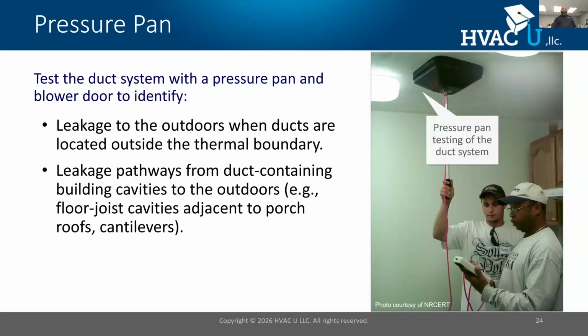All right, like LEED. All right, let's talk about one test. This is a pressure pan test. All right, a pressure pan is a calibrated, I call it a piece of plastic with a hole in it. And what it's doing, it's able to capture pressure differences across a surface. All right, the way the pressure pan works, I can pressure pan a register or grill. And this is especially useful when a duct system is in an unconditioned space. If I pressure pan that register or grill while the blower door is running, using a reference point of 50 pascals, I can then see if the duct system is leaking and communicating with the building shell.